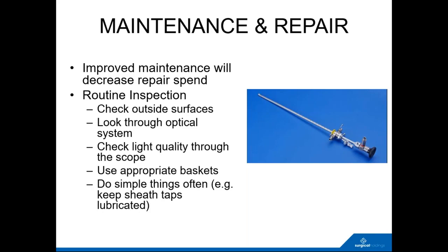You mentioned the baskets, and that's something that we see quite a lot. Obviously, when the rigid endoscopes are reprocessed, they're put in baskets that are appropriately fitted to the scopes, because quite often we'll talk to customers who assume they have the correct protective equipment in these baskets, but very often the baskets may be causing the damage themselves. Would you say that seems quite a high possibility on a lot of the small diameter scopes?